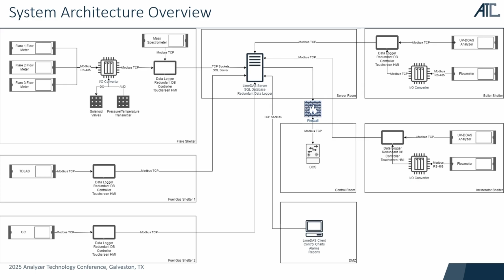So as you can see, if we start at the top left, there's various flow meters that have, in this case, RS-485 communication, so serial protocol. We would just use a very basic media converter, convert that into Modbus TCP/IP. Then above, you have a mass spectrometer. In this example, for this type of instrument, we just use a direct connection over Modbus. And then for any type of instruments like pressure and temperature transmitters, we had analog and digital inputs that, again, went from that converter to digital Modbus.